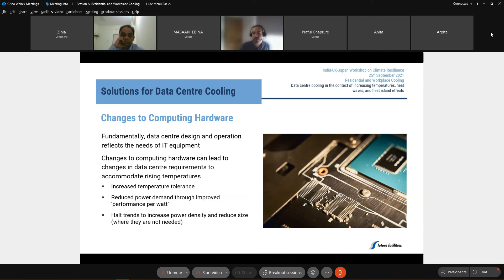But from a data center industry perspective, we shouldn't put the responsibility for changing design practice solely onto IT equipment designers. We within the data center industry also need to change our approach. Currently, it's common to use historic weather data as the basis for designing a cooling system, for example basing peak design temperatures and degree design days on the past 20 years of weather records for a location, rather than looking at what we can anticipate for the future. So really we need to look towards predicted trends so that our design can be future-proof. Some major data center operators have begun to do this, but it's really not common.